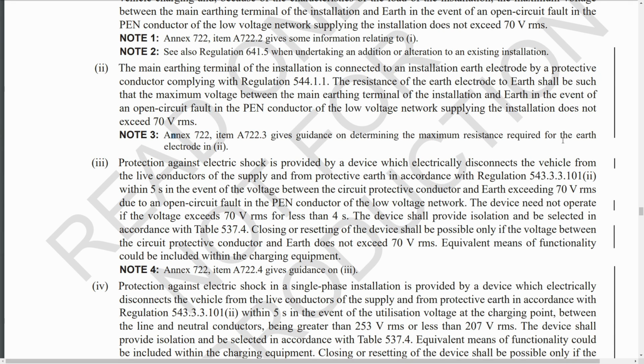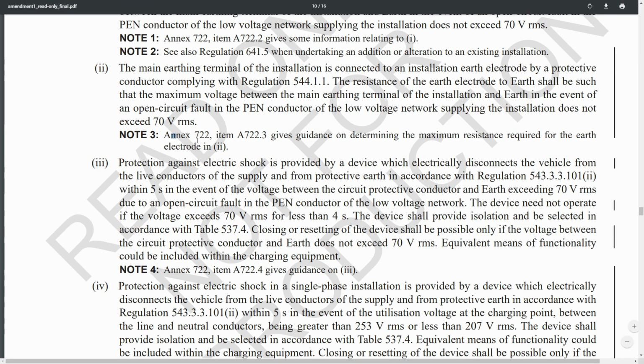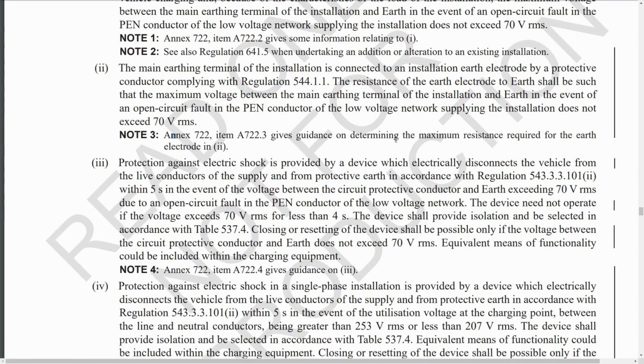So it could be done, but it's not going to be a popular option, suggesting that to have your car charging point installed, you're going to have a whole new driveway installed. But it is a practical option if you're going to have a new driveway, but otherwise not something you're going to be using in most cases. And again, it would apply to other installations as well, but say it was in a car park, in a commercial building, whatever, you would need a huge earthing mat put under the ground, obviously when the car park surface is installed. So if you can get there before the surface is put there, well, that's great. But if not, well, again, it's not going to be practical to start destroying that to put an earth mat in.